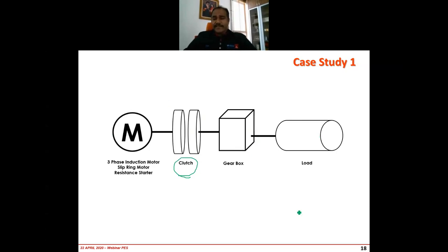So when you have this kind of system, we have to understand one thing. If you look at this, you have a gearbox here. And obviously, when we have a gearbox, we must understand that this is like a mechanical transformer. A gearbox is usually installed because they already calculated and designed from day one that they want to achieve a certain torque at the load. That's why it's running at a lower speed. They already calculated the speed and the torque requirement at the load side, so accordingly they size the gearbox. Everything is already calculated.